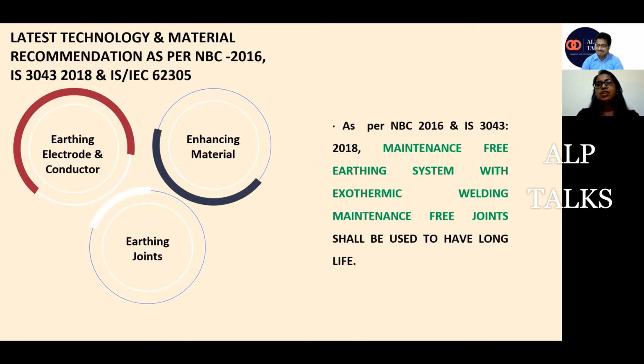I'll tell you. As I told earlier, initially there was a misconception that 2 earthing pits or 4 earthing pits would be sufficient for achieving the value. But actually it is not so. The number of pits depends upon the resistivity of that location. So for every earthing, we need to check the soil resistivity of the location first. After that, we do the calculations. Suppose I am getting 100 ohm meters of resistivity at one location, or 70 ohm meters at another. I'll check with 70 ohm meters of resistivity: if I'm going for the maintenance free earthing system, in how many pits am I able to achieve less than 1 ohm.